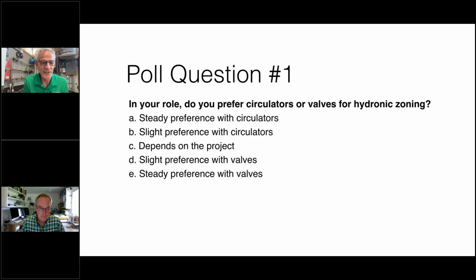Yeah. It wasn't intended to run down at that lowest speed. Now they're getting better with the electronic pumps and stuff, but it just doesn't make a lot of sense to me to move such a small load with a dedicated circulator. Sure. And I found over the years too, just to your point, personal preferences. I've met contractors who do everything with zone valves. I've met contractors who do everything with zone circulators.